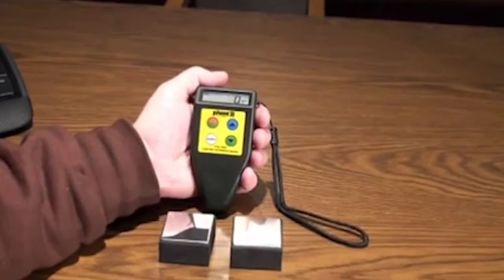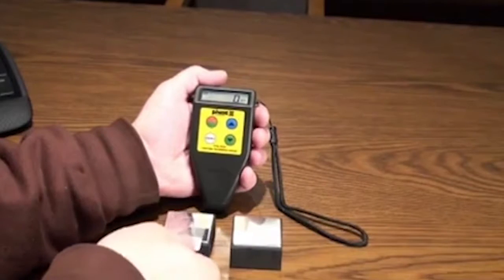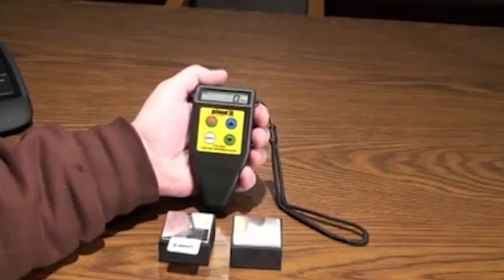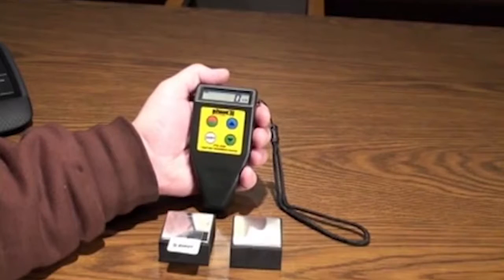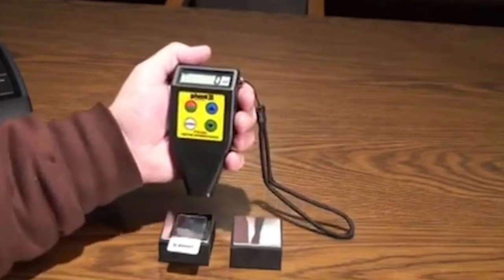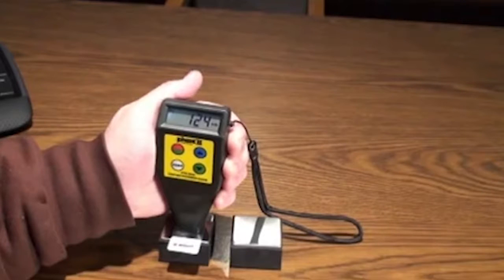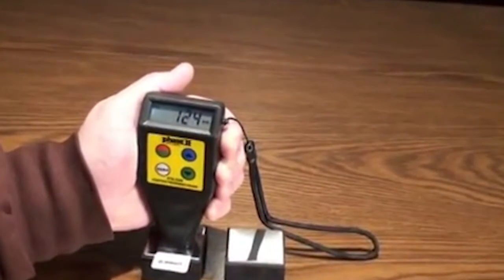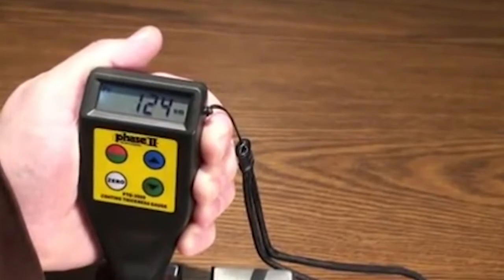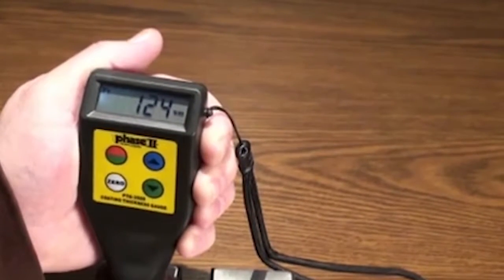Now select a calibration standard that is similar to the coating thickness of your application. Place it on top of the steel substrate sample. Then place the probe over the standard and press firm to flat. Readings will display on screen. Notice the FE showing on the left of the screen. This signifies that the substrate used was ferrous.